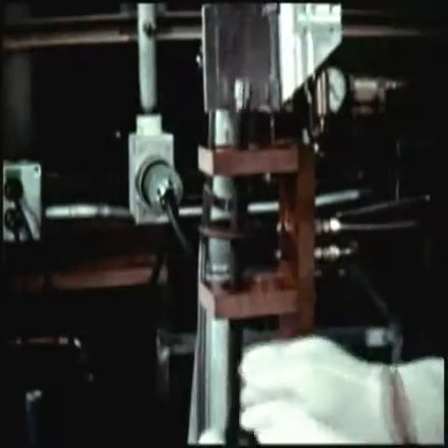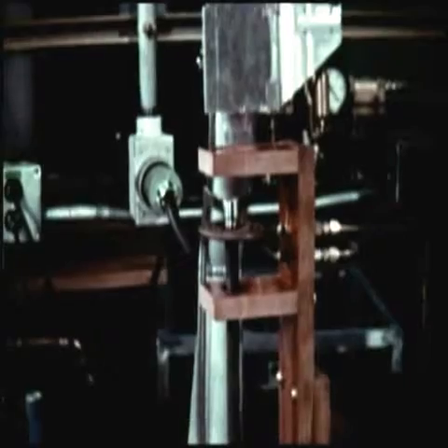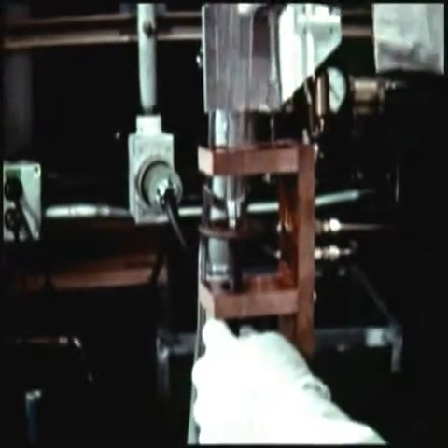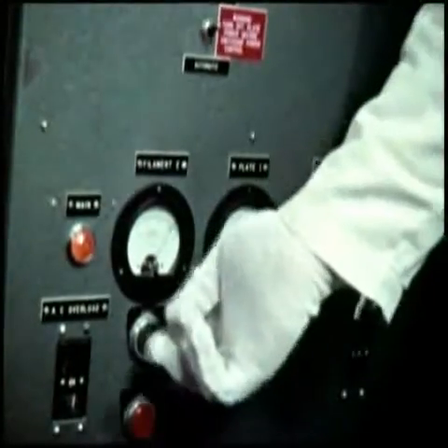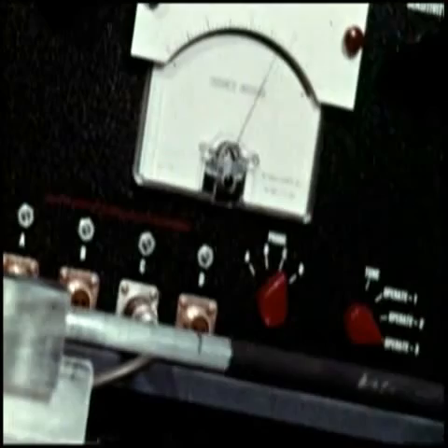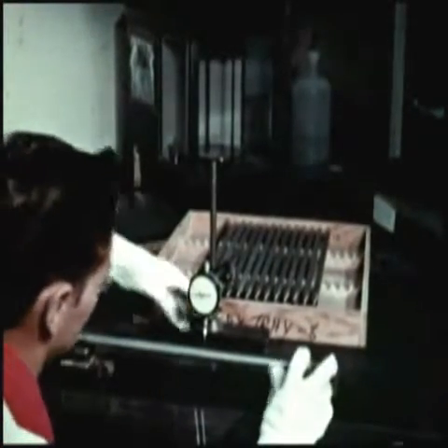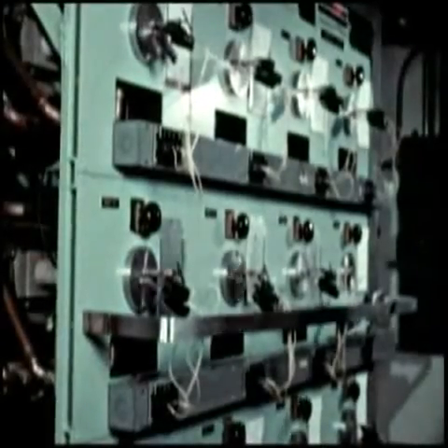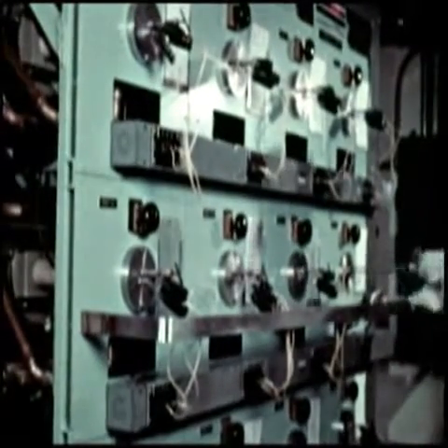A similarly coated end closure cap is placed in the end of the tube. This ceramic coating reduces loss of hydrogen by diffusion through the cladding tube by several orders of magnitude. Quality control checks are sequenced throughout fuel element manufacturing to conserve material and assure reliability of the final product. These specially designed furnaces are used for checking hydrogen losses at reactor operating temperatures.